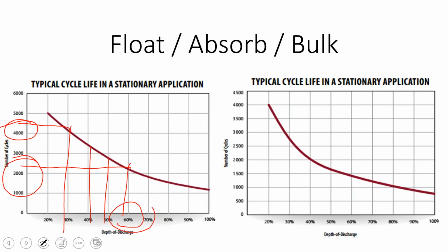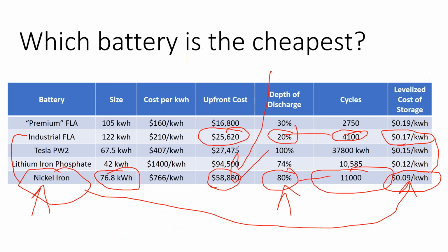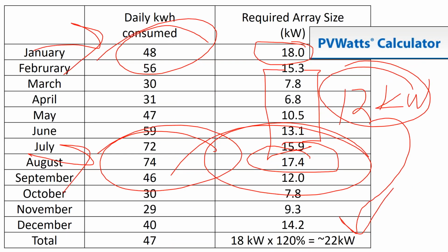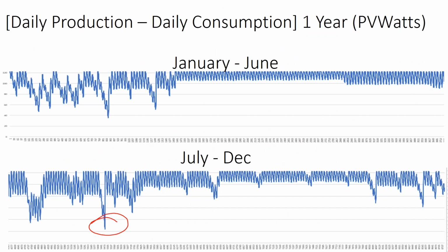If you oversize it by 50%, more than likely the worst thing that'll happen is you spend more money, but the battery is going to last 50% longer as long as it's well maintained. So oversizing the battery is not that big of a deal, other than the system becoming unaffordable.